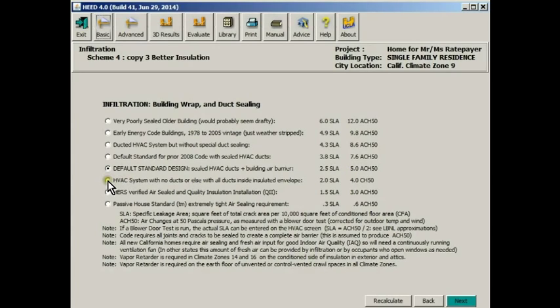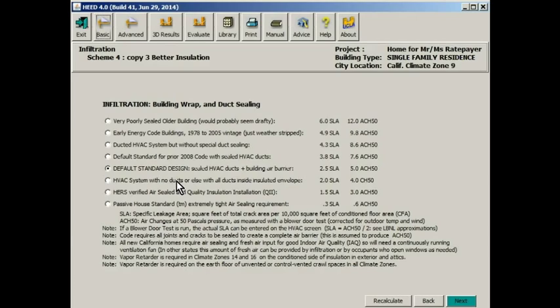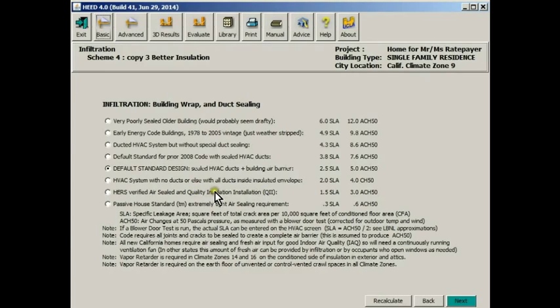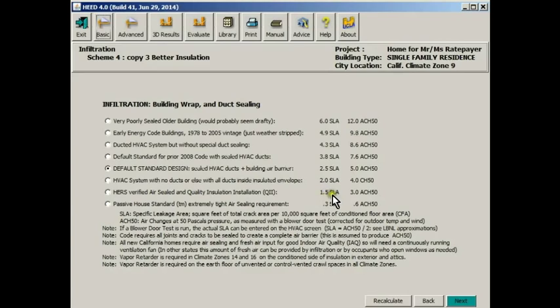This is the infiltration screen that speaks to the tightness of the building. The new California Energy Code has increased the requirements for building tightness, so the infiltration will be less. The specific leakage area has now got to be less. The air changes at 50 Pascals pressure difference is five air changes per hour now. We could, to tighten up our building still further, design it so that the HVAC system has no ducts. That is to say it's a ductless system, or that all the ducts are inside the insulated envelope. We could make it even tighter by saying that we were going to have a HERS inspector check the building in a couple of places during construction to ensure quality insulation installation. And that should give us a 1.5 specific leakage area with only three air changes per hour at 50 Pascals.